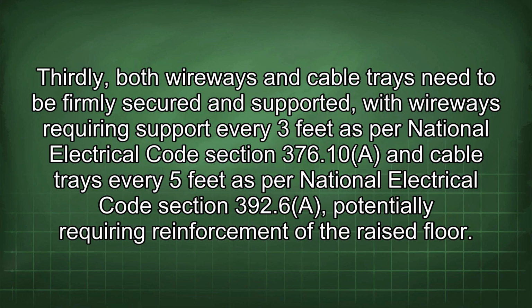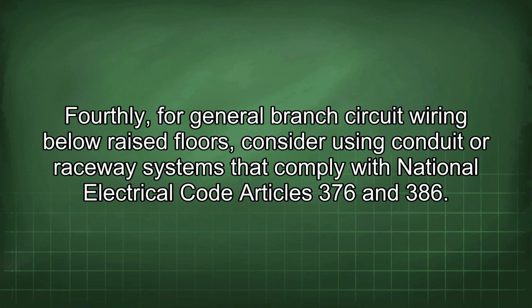392.3. Thirdly, both wireways and cable trays need to be firmly secured and supported, with wireways requiring support every 3 feet as per National Electrical Code Section 376.10 and cable trays every 5 feet as per National Electrical Code Section 392.6(A), potentially requiring reinforcement of the raised floor. Fourthly, for general branch circuit wiring below raised floors, consider using conduit or raceway systems that comply with National Electrical Code Articles 376 and 386.